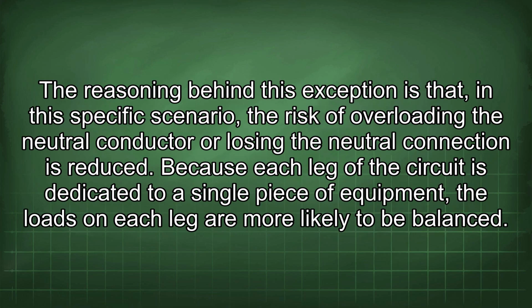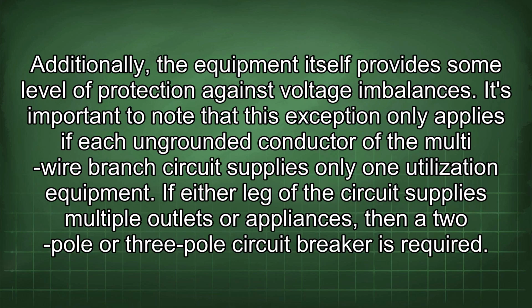The reasoning behind this exception is that, in this specific scenario, the risk of overloading the neutral conductor or losing the neutral connection is reduced. Because each leg of the circuit is dedicated to a single piece of equipment, the loads on each leg are more likely to be balanced. Additionally, the equipment itself provides some level of protection against voltage imbalances.